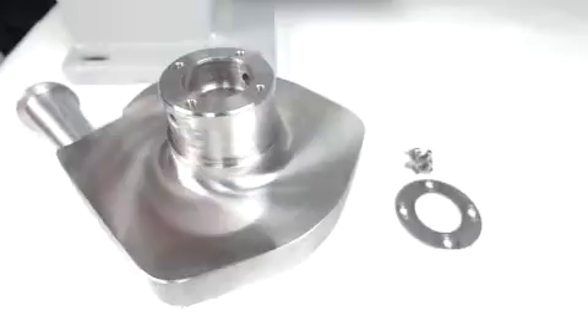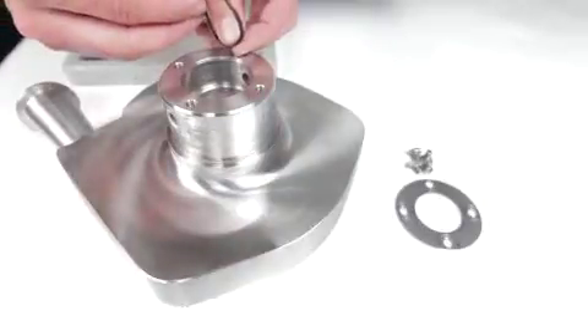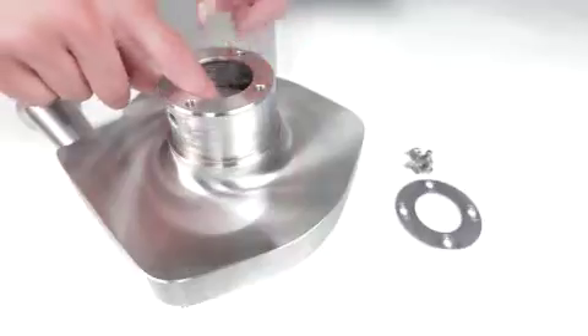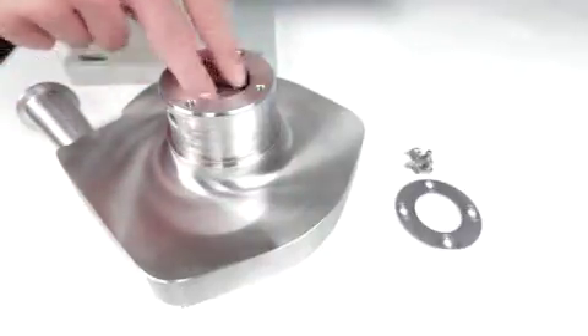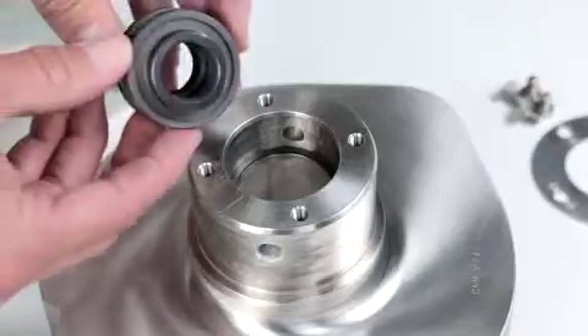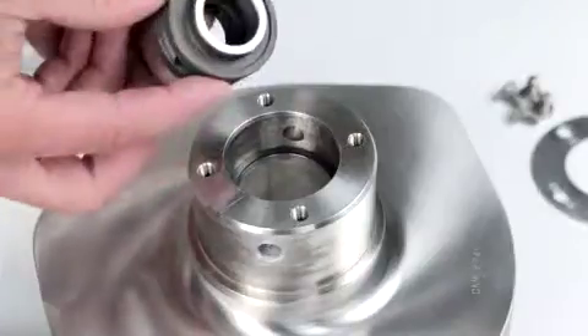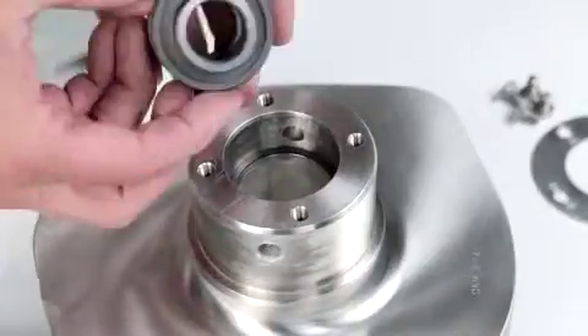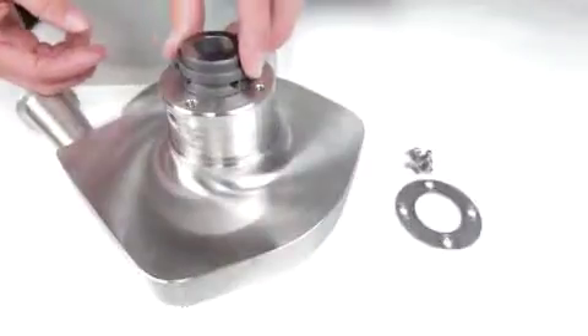To install the stationary seal into the hub of the pump housing, place the pump housing on a clean surface with the hub side up. Inspect the hub area to ensure that it is clean. Place the flat gasket into the hub of the pump housing. Make sure that it is all the way to the bottom and that it is seated evenly. Install the stationary seal into the housing hub with the small face entering the hub first.